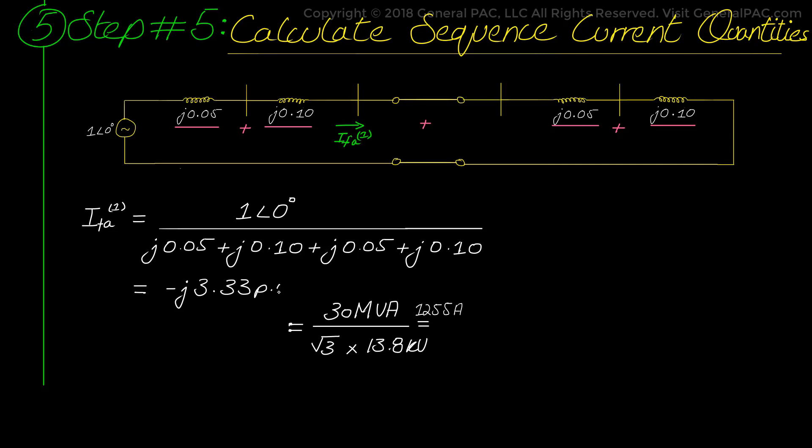Now we must calculate the current value in amperes. So, first we take the base value of power which is 30 MVA divided by the base value of the voltage at the faulted end, 13.8 kV which gives us the base value of current at 1255 amperes. Multiply that base value of 1255 amperes by the per unit and we actually get the ampere current that is flowing through the positive sequence network. And that is 4184 at negative 90 degrees.